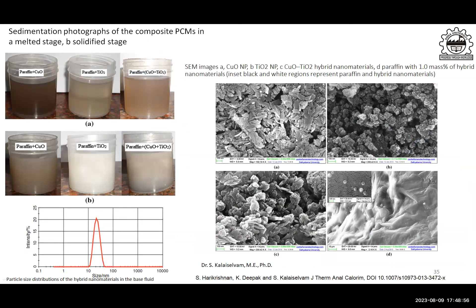This is an CuO-TiO2 hybrid nanocomposite phase change material. We need to know the limit of mixing this nanomaterial into the phase change material, which is a maximum of 0.8%. Beyond that, there may be a decrease in latent heat and an increase in viscosity, which affects the performance of the phase change material.